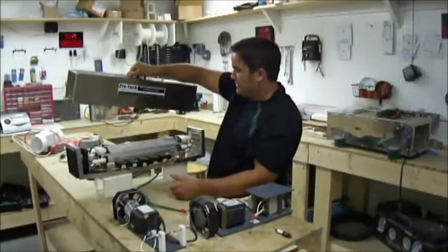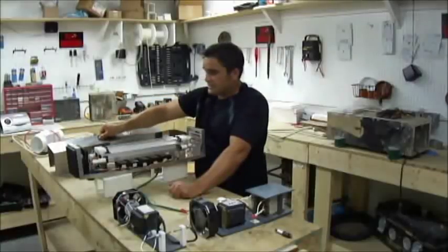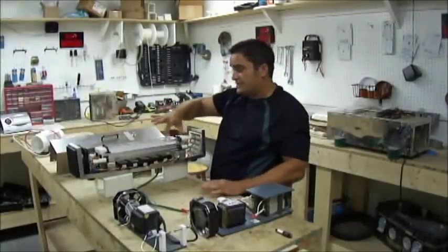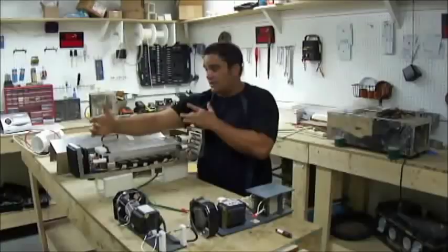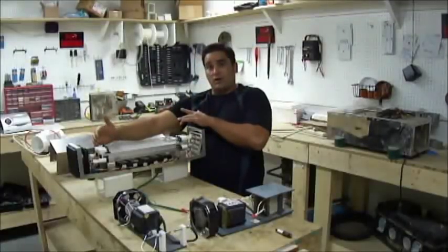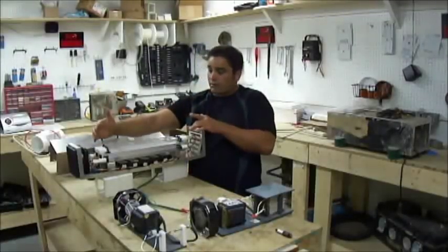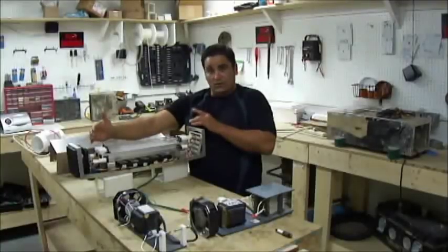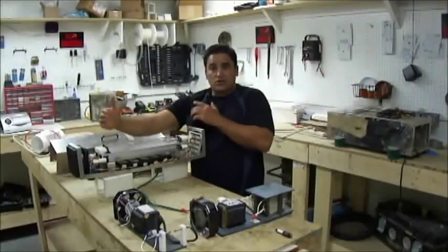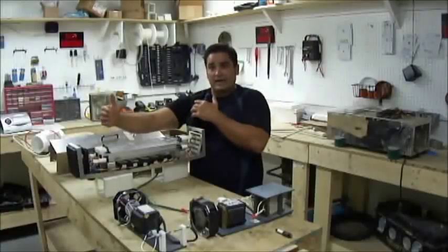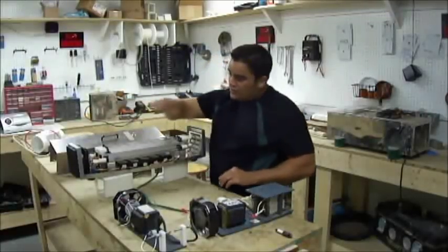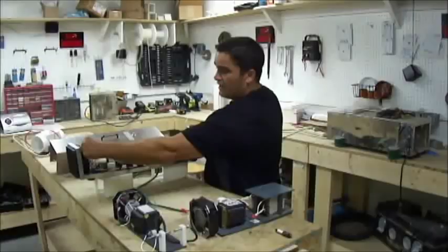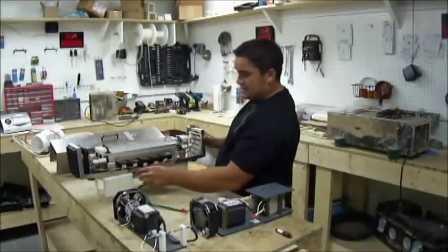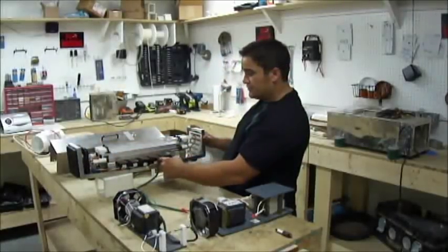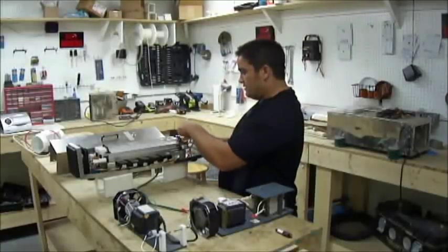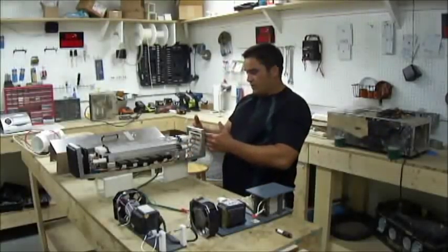So when you lift this hood off and expose the inside, you see that there are a series of special frequency light bulbs. And when these light bulbs are exposed to air, it'll create ozone gas. The ozone is created in low volume, not high volume, however. So in this machine, you can see a computer fan at one end. Then you have a series of ballasts, which transform the current. And then you have the light bulbs. And at the other end, we have the outlet.